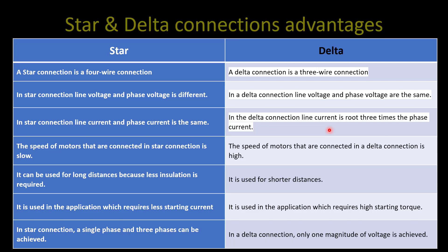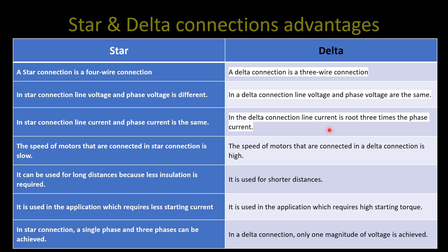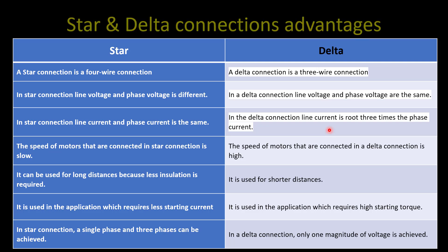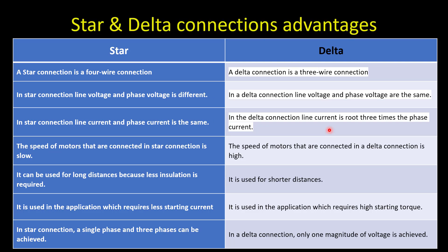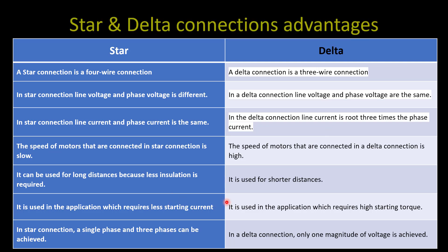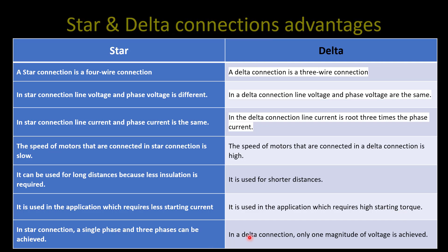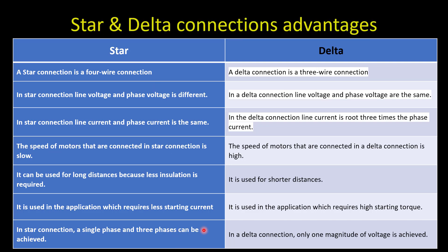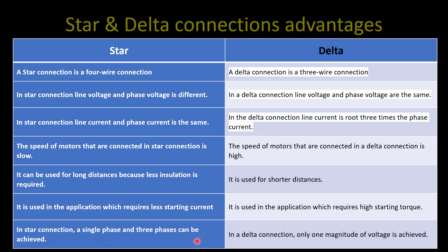Comparing star and delta connection: star connection is a four-wire connection; delta connection is a three-wire connection with no neutral. In star connection, line voltage and phase voltage are different; in delta connection they are the same. In star connection, line current and phase current are the same; in delta, line current is root 3 times the phase current. Speed of motors connected in star is low; in delta it is high. Star is used for long distance because less insulation is required; delta is for shorter distances. Star is for applications requiring less starting current; delta requires high starting current. In star, both single-phase and three-phase voltages can be achieved; in delta only one voltage magnitude is available.